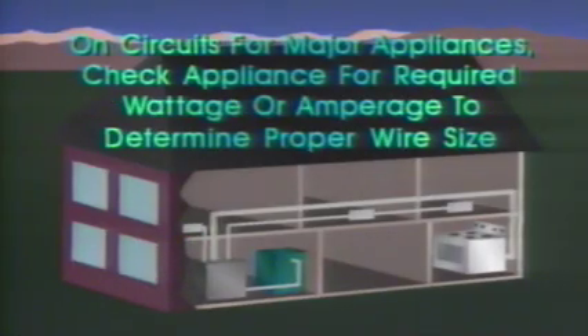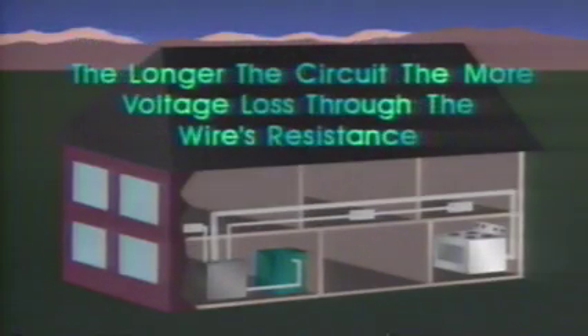When planning a special 120-volt circuit, find the wattage or amperage for the equipment on the nameplate if listed. Then determine the required wiring for the circuit. The longer a circuit extends, the more voltage will be dissipated in overcoming the wire's resistance. When the circuit is excessively long, the voltage drop may be so great that an insufficient current reaches the appliance at the far end of the circuit. This could cause the appliance to run poorly or damage it.